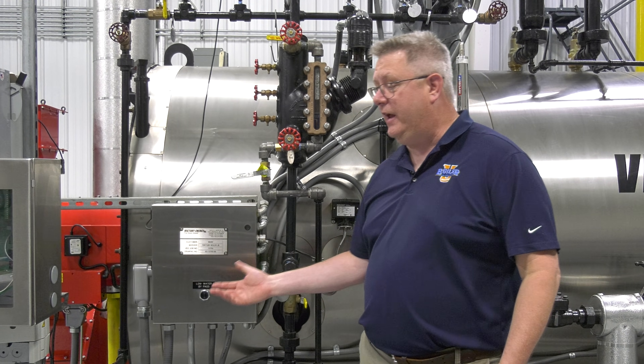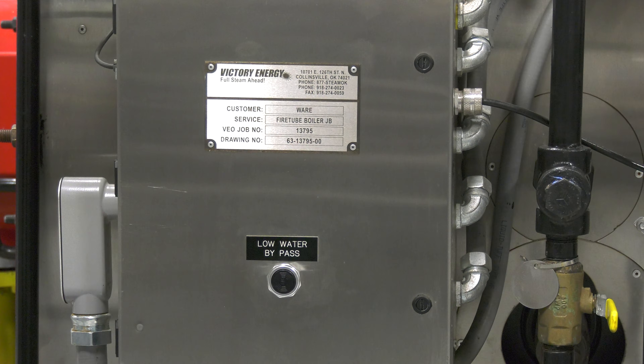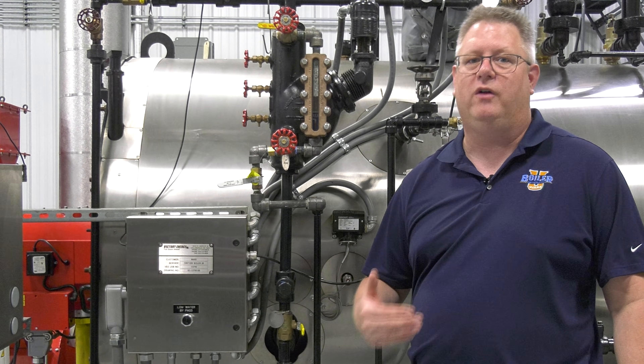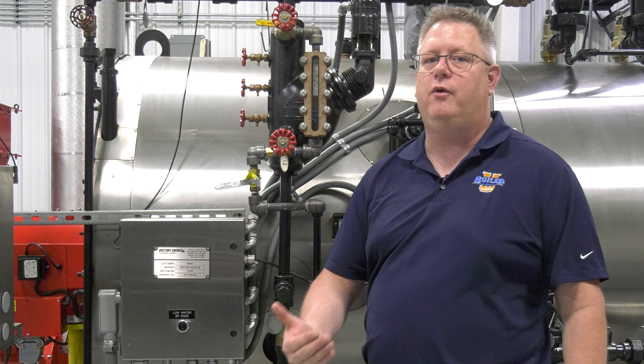On the other hand, a shunt button is very valuable if we have a single large boiler that's carrying a massive load. It's obviously not going to be best for production to shut that boiler down every day, or once per shift, or whatever frequency we're doing the blowdown.